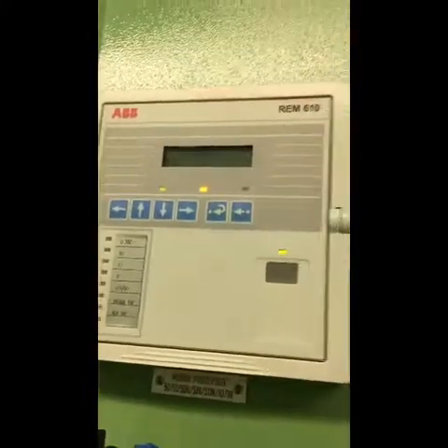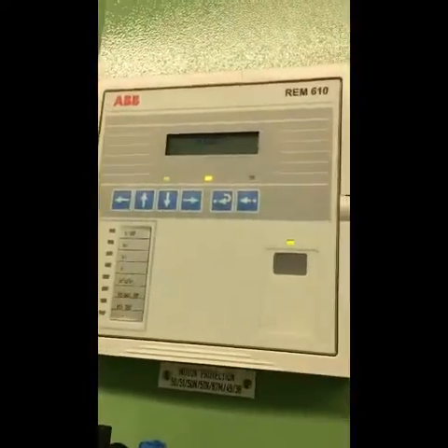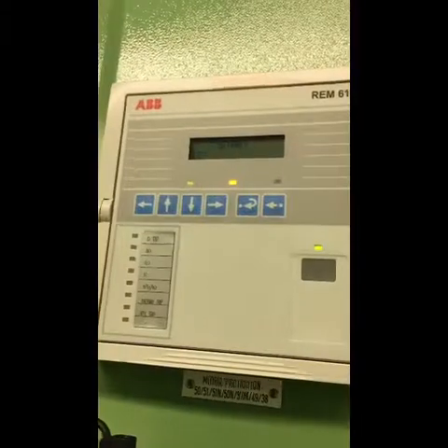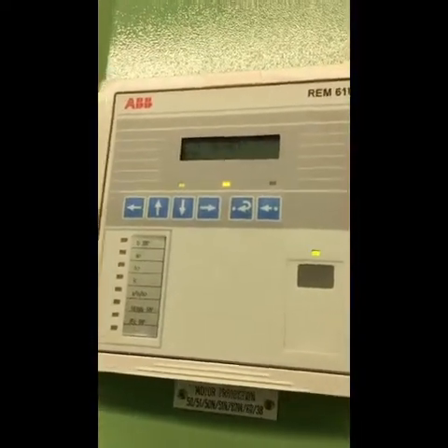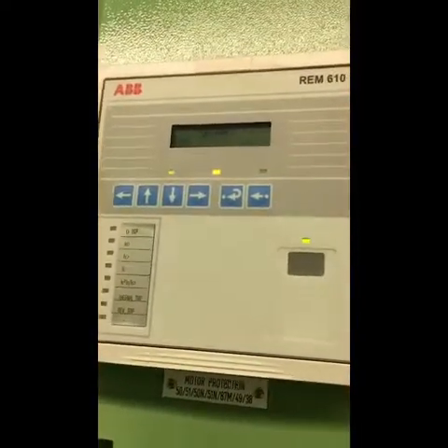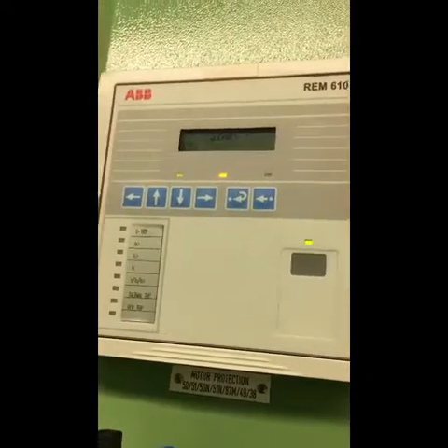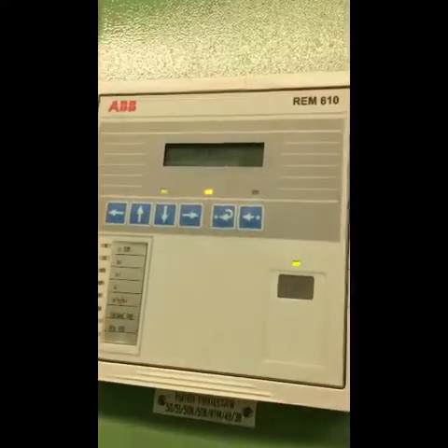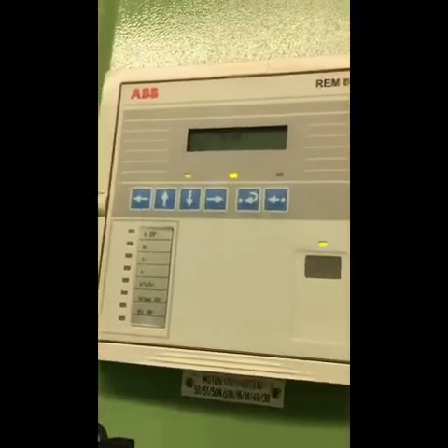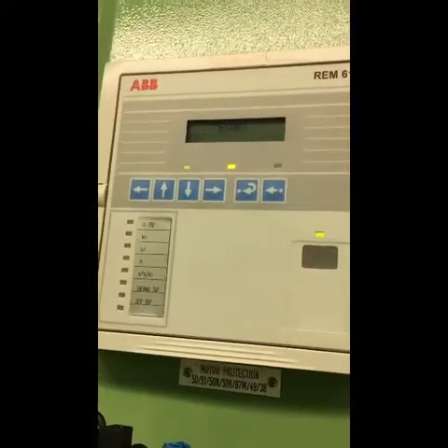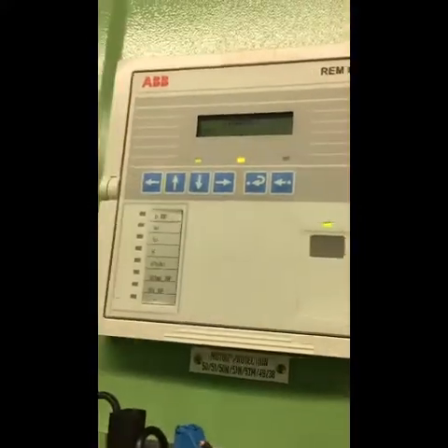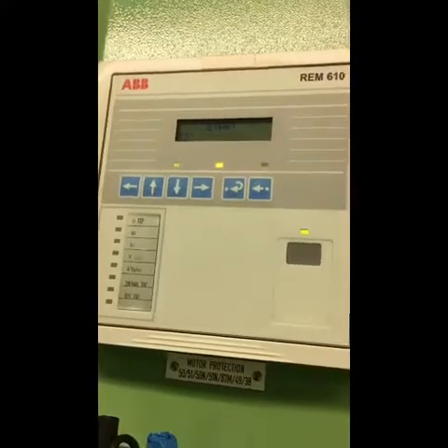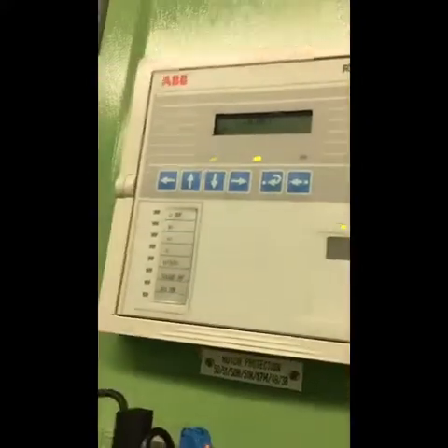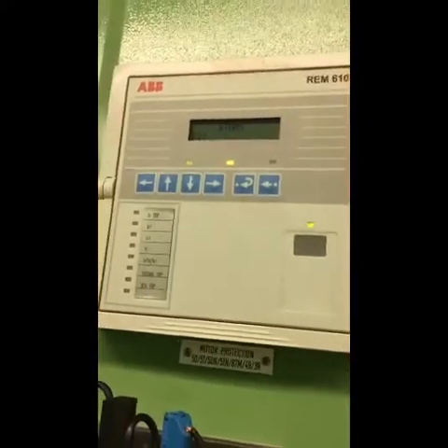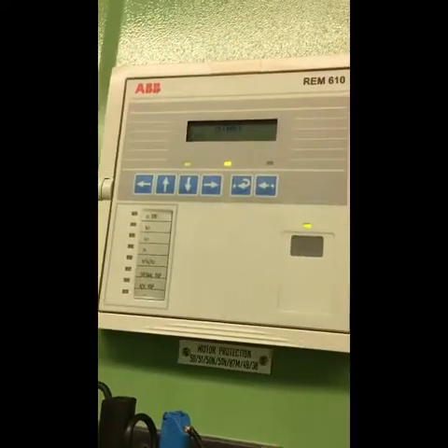When I see this message, it shows that there is an alarm of I2 greater. It means there is something wrong with the current reading, unbalanced, or maybe one phase broken. It is in the alarm mode now. It will continue in the alarm mode until it reaches the tripping value, the tripping time. So we will see when it trips, and we will read the current.